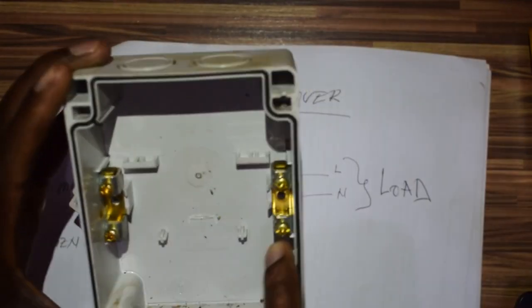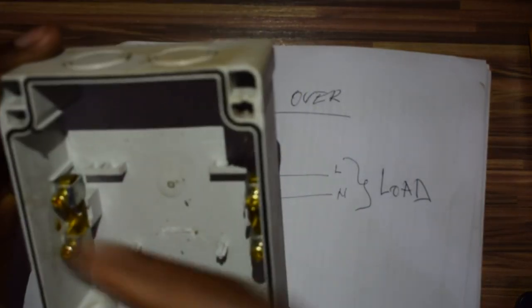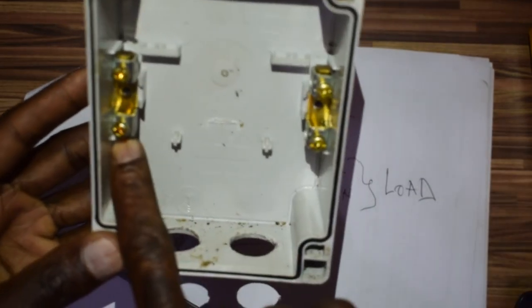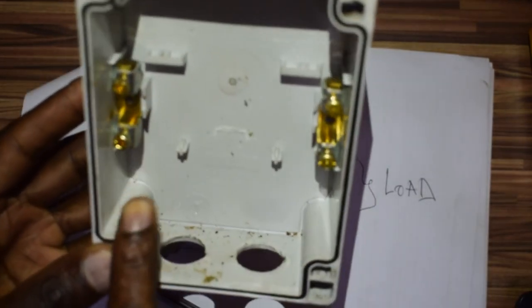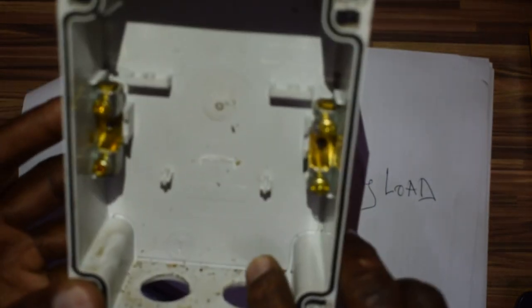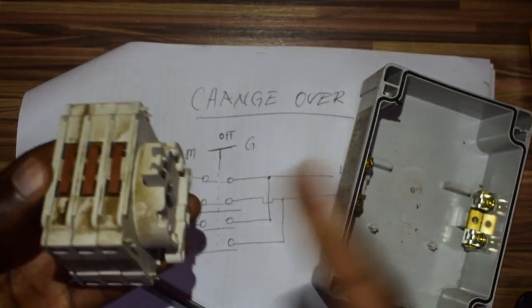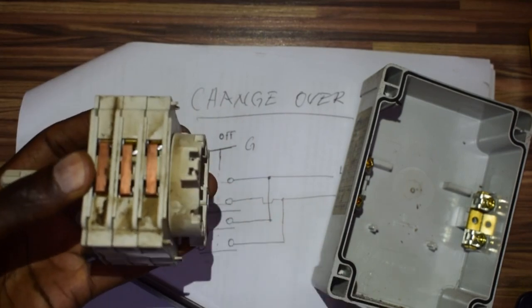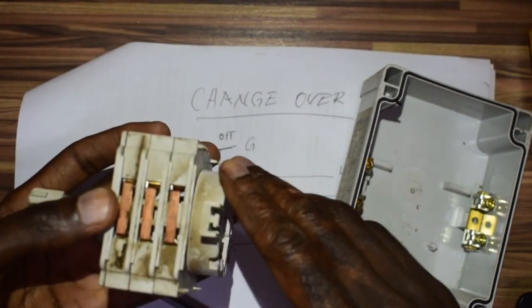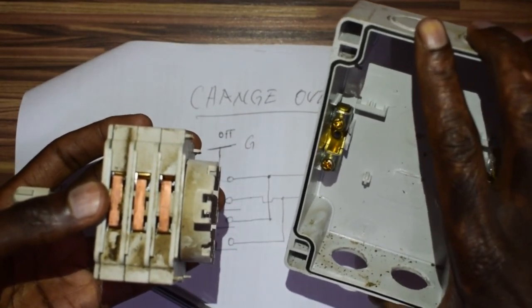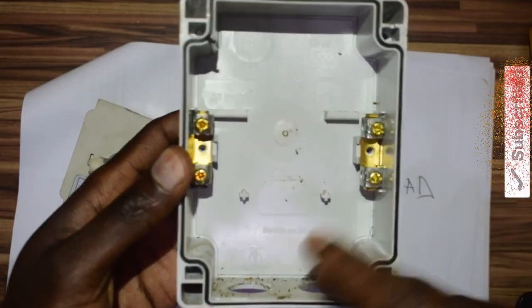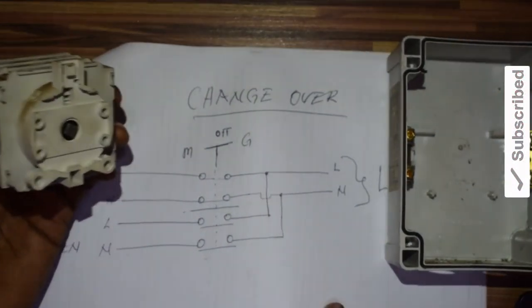In case you're using it for three phase, they've given you these two contacts - you can use one for neutral and the other for earth if you want. But normally in changeover, we like to break everything. If you're breaking, you have to break all the lines and the neutral. It's good that way. But if you don't care about that, you can just feed in your neutral here and your earth here.